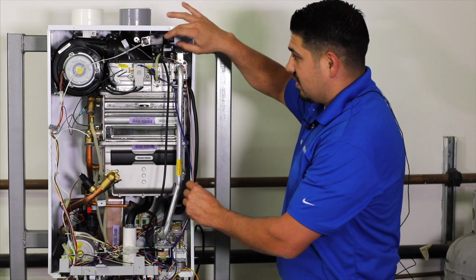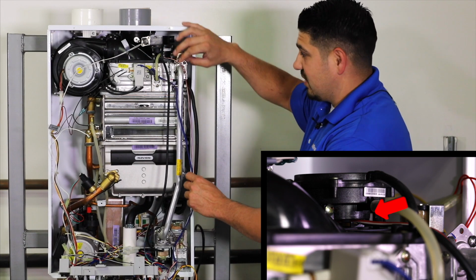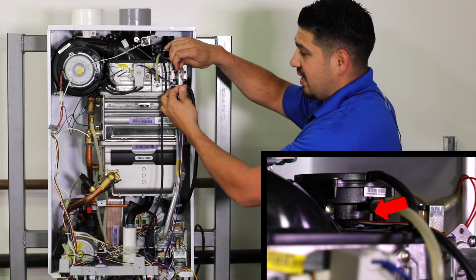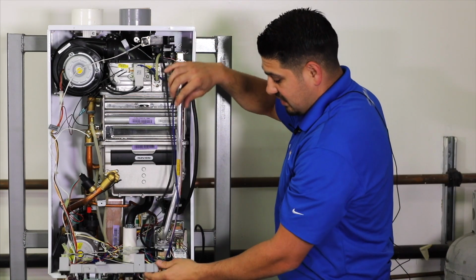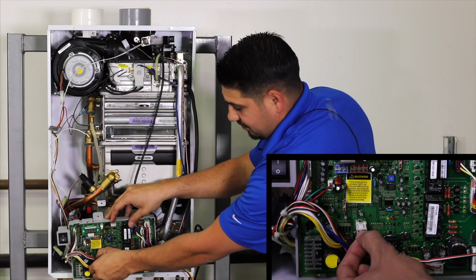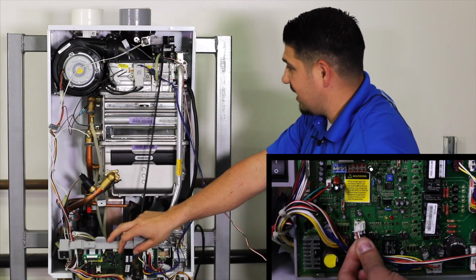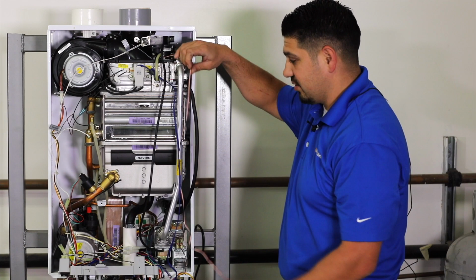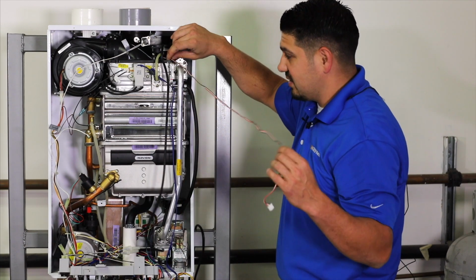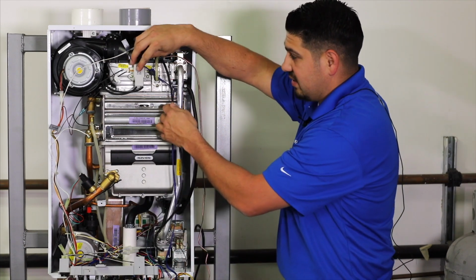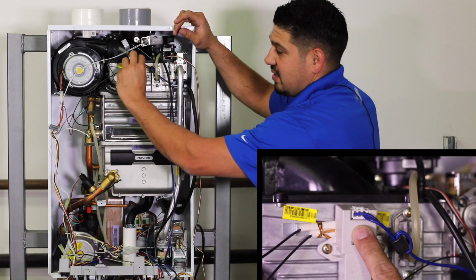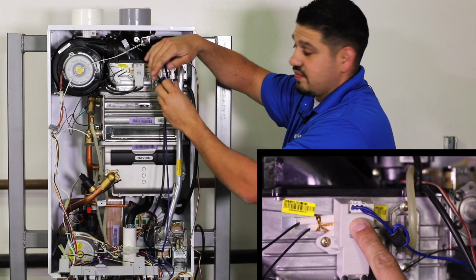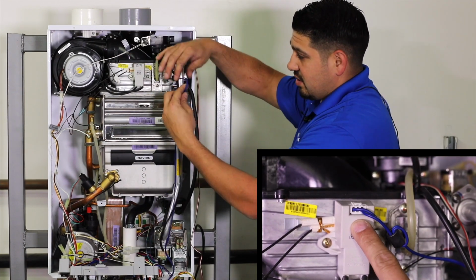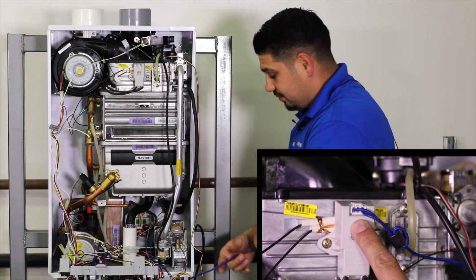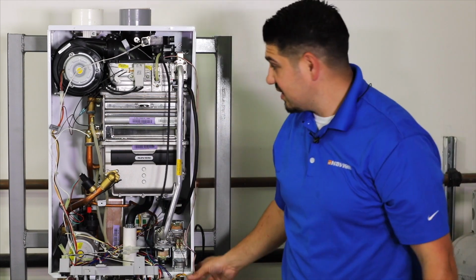There's your air pressure sensor. It has a red, black, and white wire. That connects to the front of your computer board. So we're going to go ahead and disconnect that. Be careful with your computer board. Now that one's disconnected. And on this side, the last thing we have to do is go ahead and disconnect your ignition transformer, which is this blue wire here. So that should do it for the other side.